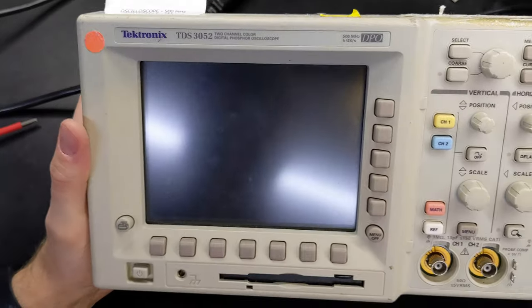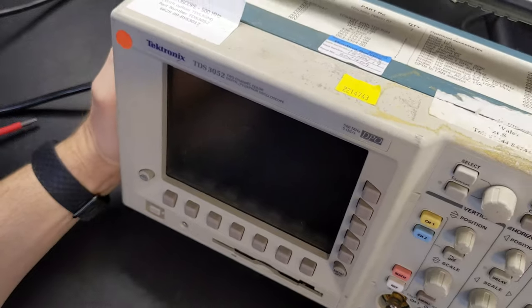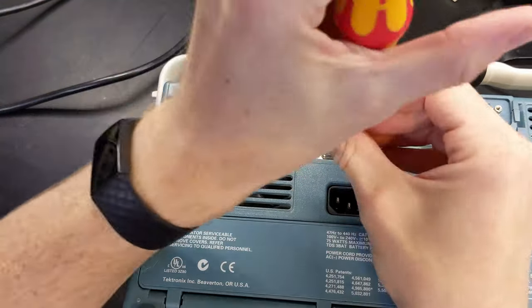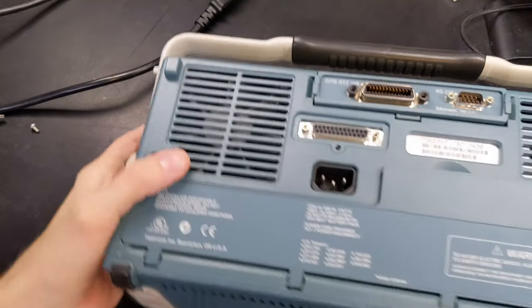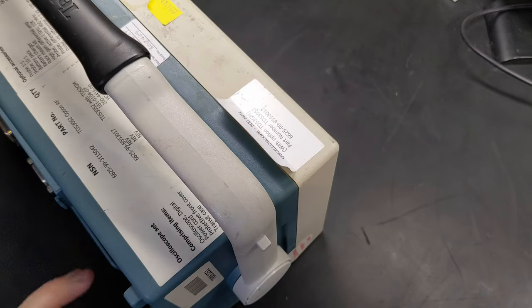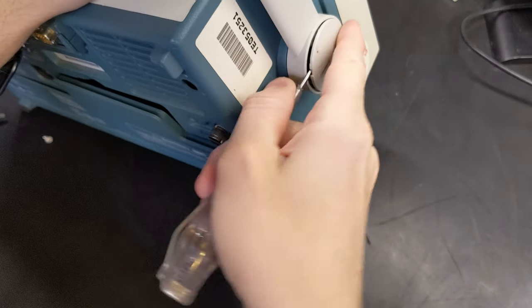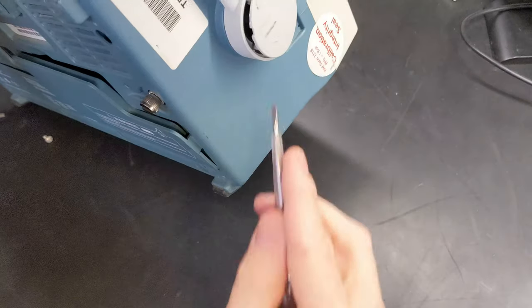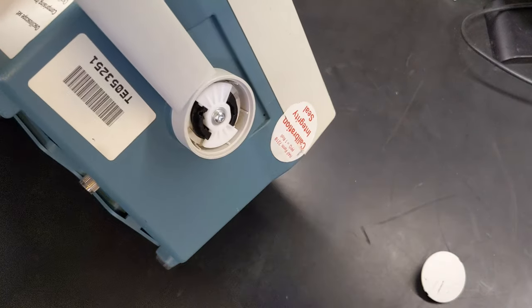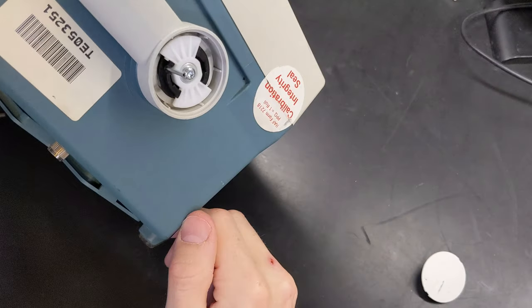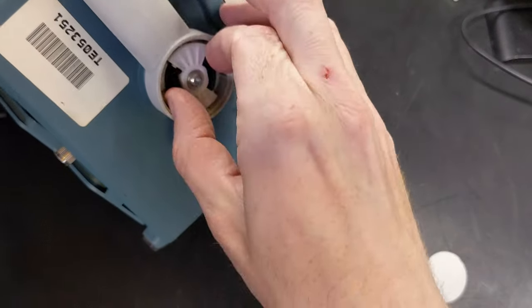This scope has been torn down by the EEV blog and I'll link to that down below. They talked a little bit about how to open it but didn't really tell you because this has got one of the weirdest opening systems I've ever seen. So you have the single screw here that you have to remove. Once that screw's out, what you then have to do is go to the side of the case where there's the handle and you have to grab a screwdriver and lever out this cover.